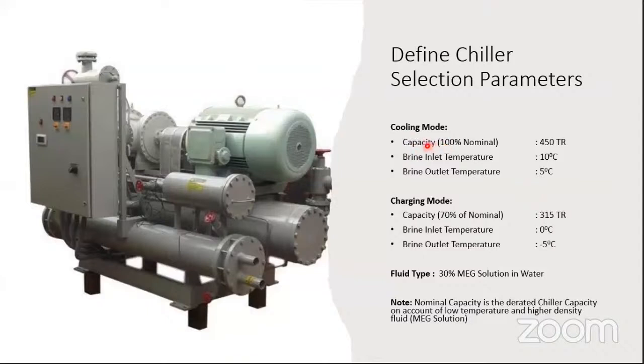And this is basically the chiller specifications. Your chiller should be able to deliver 450 tons as a nominal capacity, and it should be able to deliver this at these temperatures. Brine outlet temperature is 5 degrees centigrade and inlet temperature 10 degrees centigrade. At these temperatures, I should get these. Plus, I should also specify that in charging mode, my chiller capacity should be this much. This is how much I need, 315 tons, at these charging temperatures, 0 and -5. I should also specify to him what fluid type I'm using.